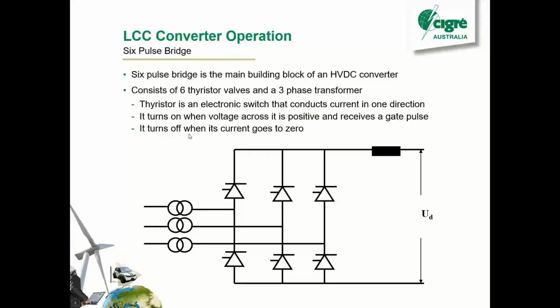So this is the key point. You can't make a thyristor turn off. You have to force it externally to turn off. That causes a lot of the problems that we have with the LCC. The VSC uses IGBTs, which you can force to turn off, and that solves a lot of the problems. A thyristor is basically just a diode, but you're able to decide when it turns on. That's the difference.